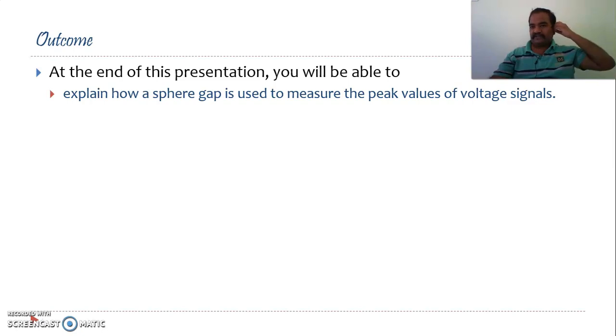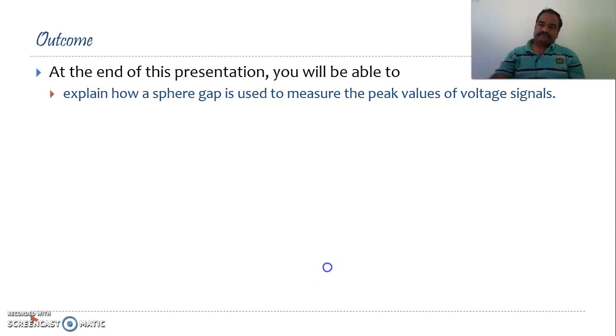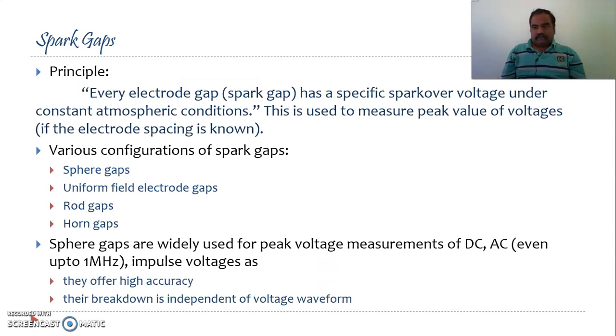Today's class is aimed at using sphere gaps particularly for the measurement of peak values of signals. By the end of this presentation, I hope you will be able to explain how a sphere gap is used for the measurement of peak values of a given voltage signal. It works on a very simple principle: every electrode gap or sphere gap has a specific spark-over voltage under given atmospheric conditions. This principle is used to measure the peak value of the given voltage signal if you know the electrode spacing.